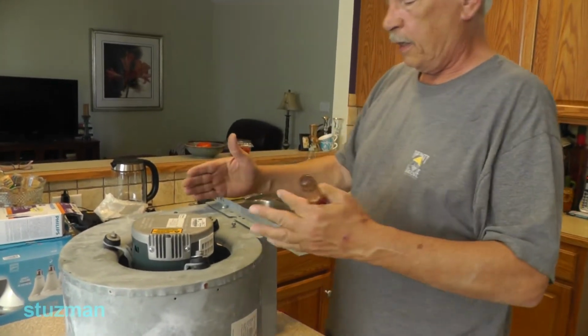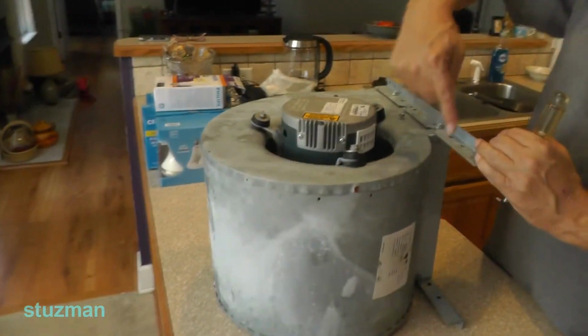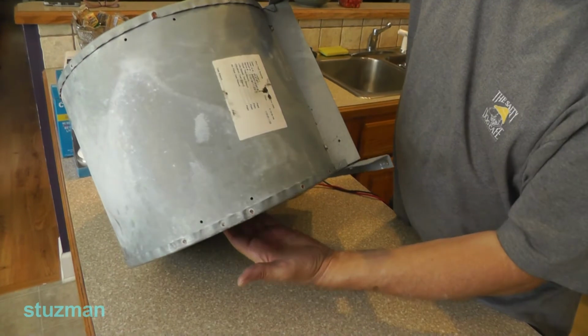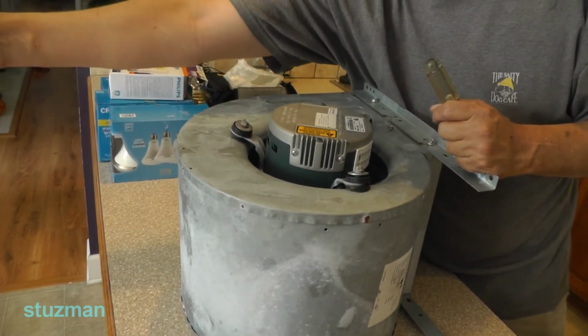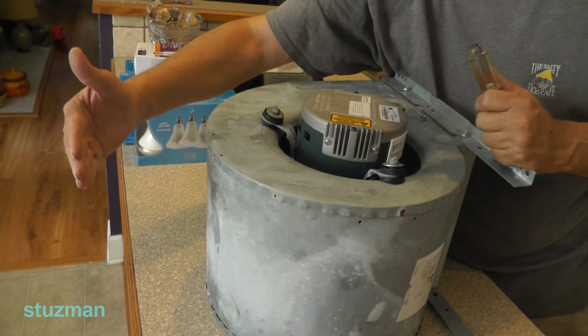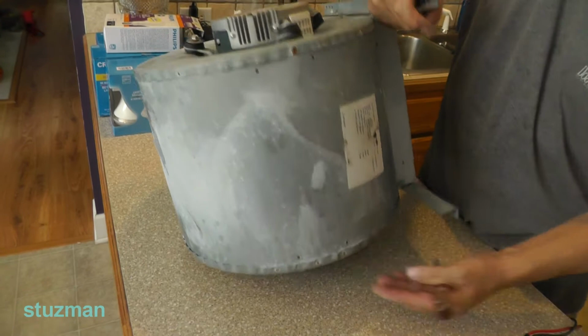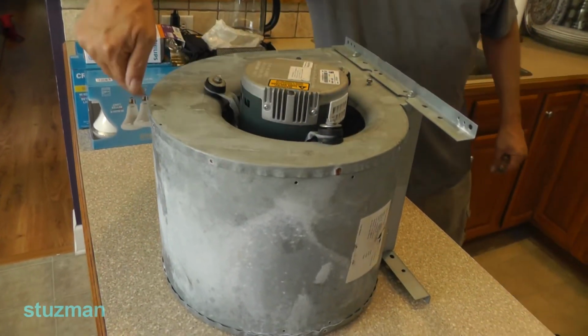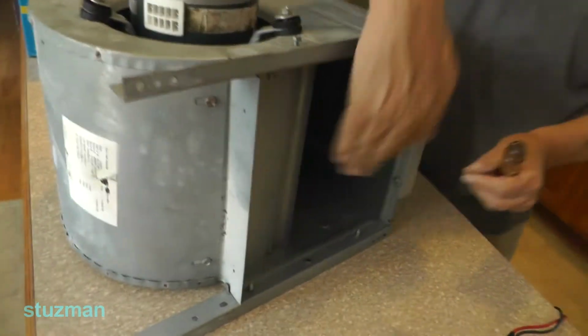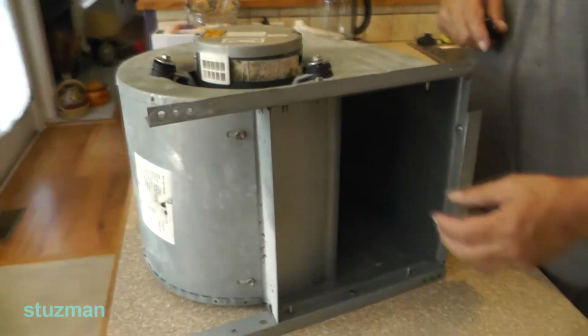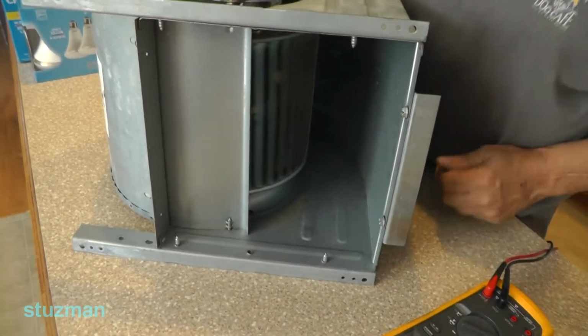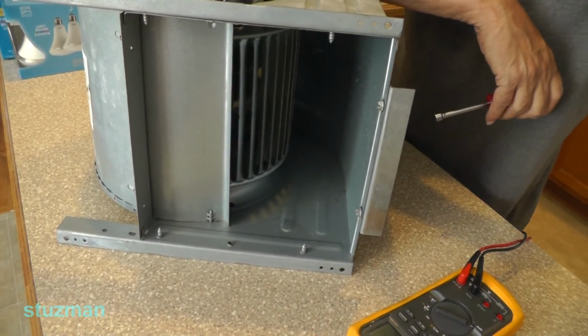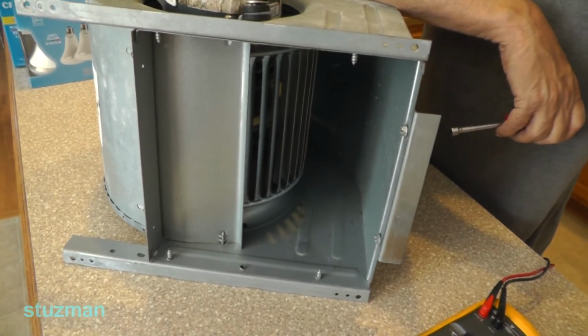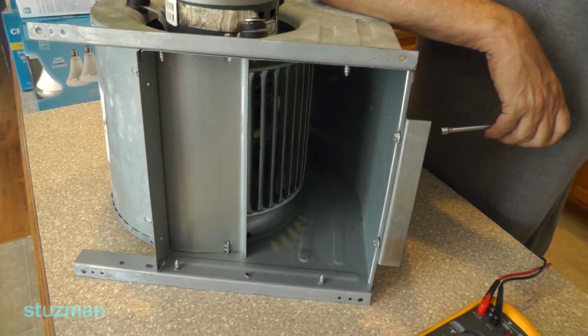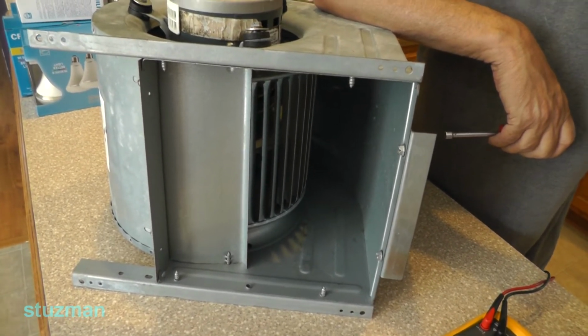Now, if you look at this, you can pretty much tell that the fan motor needs to go this way. It picks up the air inside - this is the air intake. My evaporator is over here. It's pulling the air from the other side of the evaporator, from the return, pulls it through the evaporator, comes up underneath the fan, goes in here, turns, and comes out this way - this is our supply, going to our supply duct. Now the only problem is my fan is going that way, so it's very little airflow. If you check your vents, you will see you actually do have airflow - it will have a little airflow, but it is very, very low. It's enough to cause the evaporator to freeze.